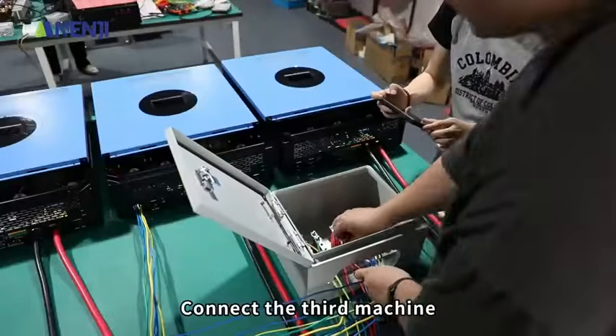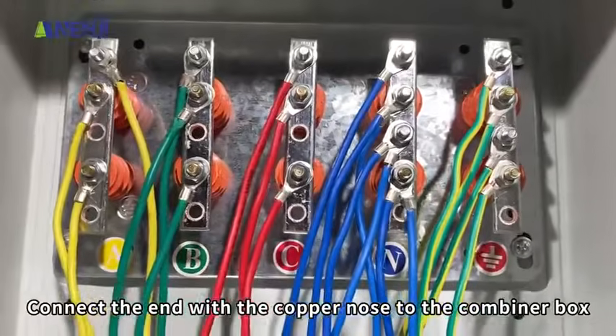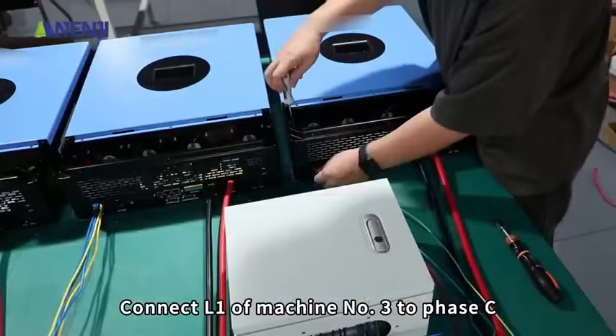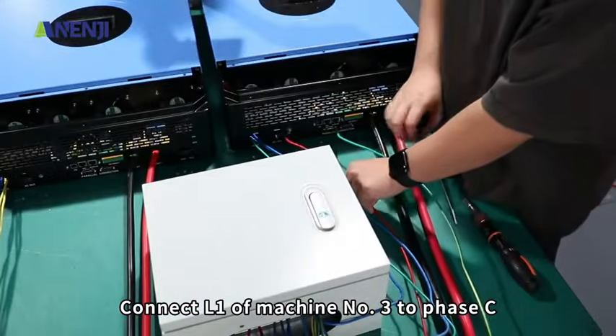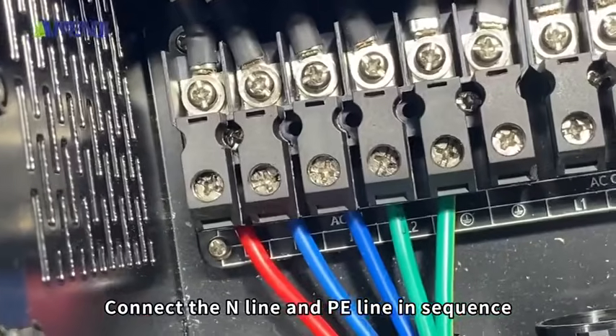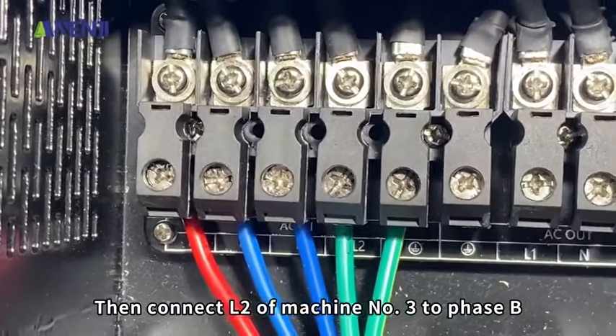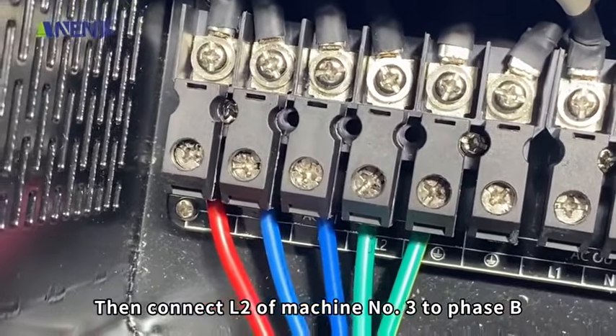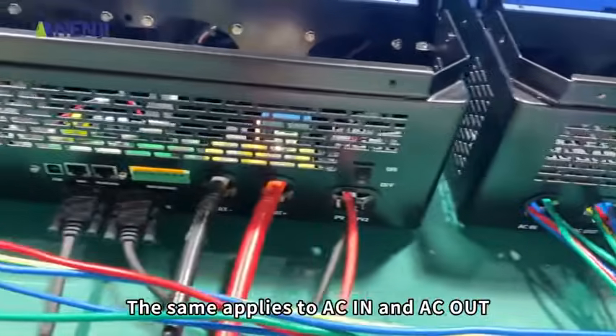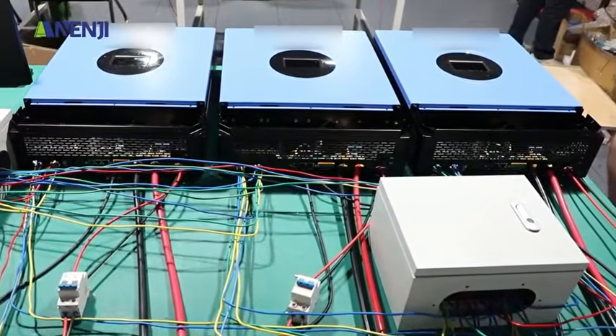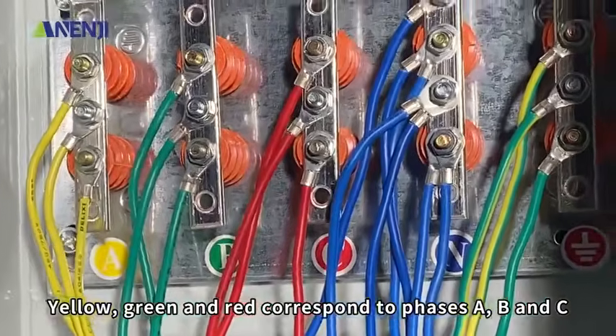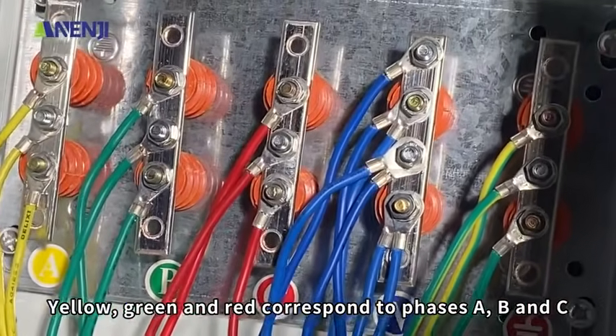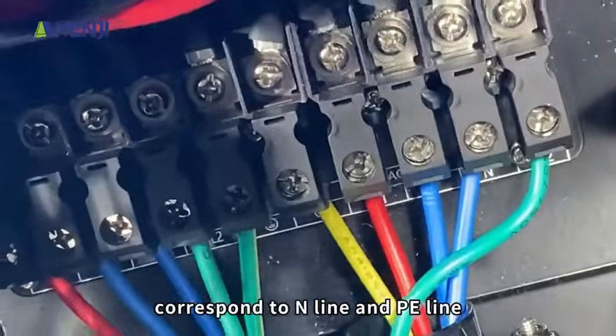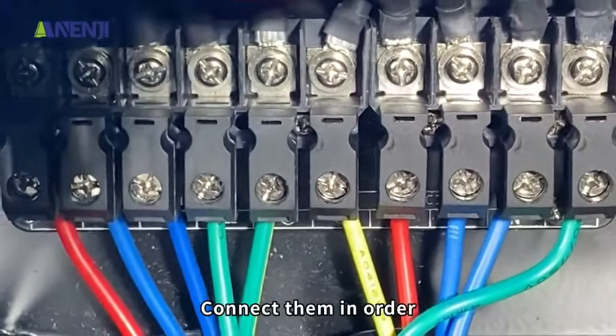Finally, connect the third machine. Connect the end with the copper nose to the combiner box. Connect L1 of machine number 3 to phase C. Connect the N line and PE line in sequence. Then connect L2 of machine number 3 to phase B. The same applies to AC in and AC out. Yellow, green, and red correspond to phases A, B, and C. Blue wire and yellow-green wire correspond to N line and PE line. Connect them in order.